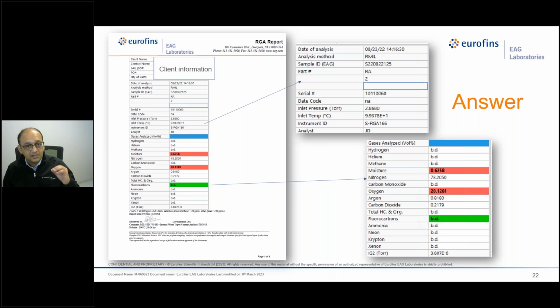But our sample chamber is at constant volume, so we can estimate the actual volume inside your sample. So this inlet pressure is a critical quantity for us to understand what kind of calibration factor we need to use, because our calibration factor is based on the standard volume of the gas, and depending on the pressure, the volume of the gas changes and the set of calibration factors would change. So we monitor that for each individual sample.